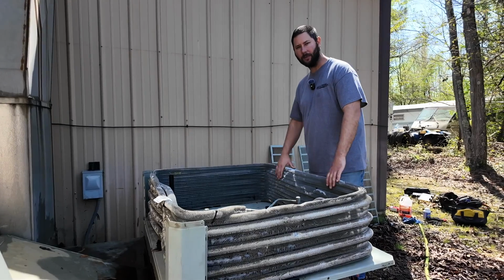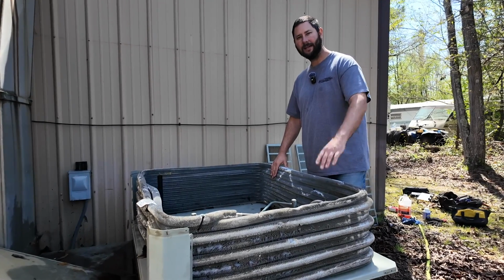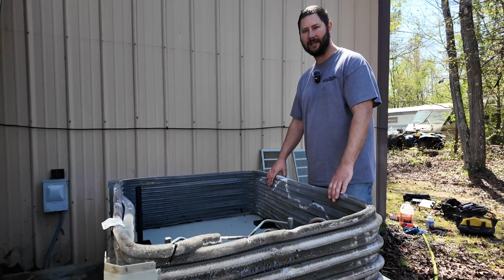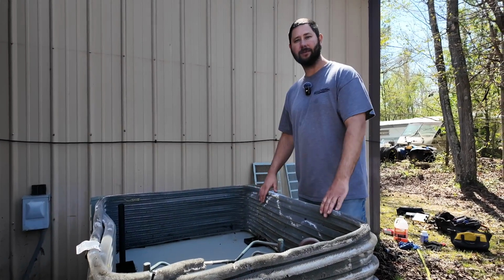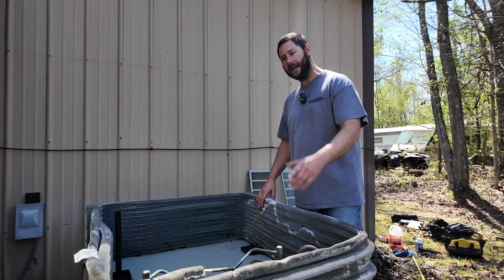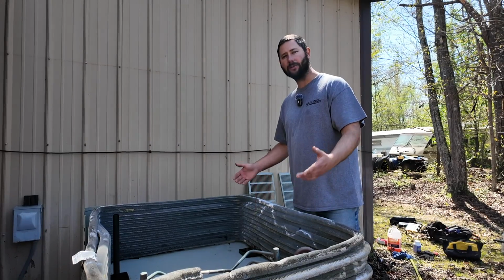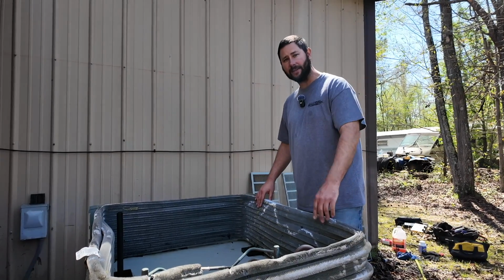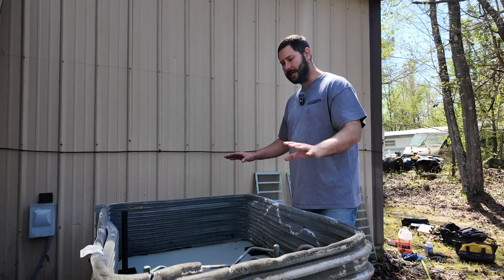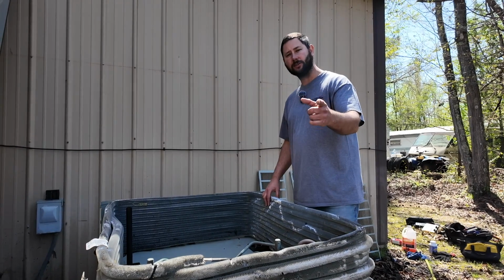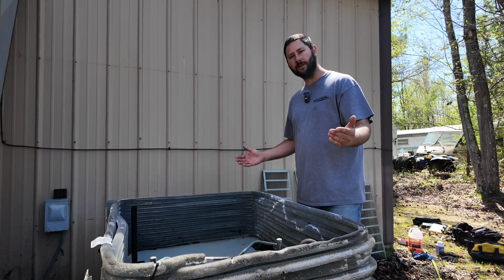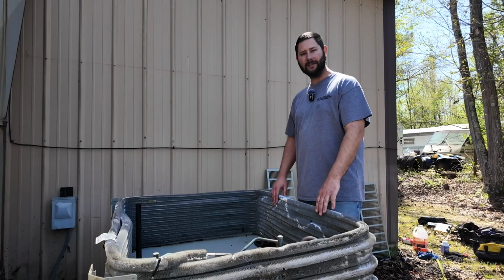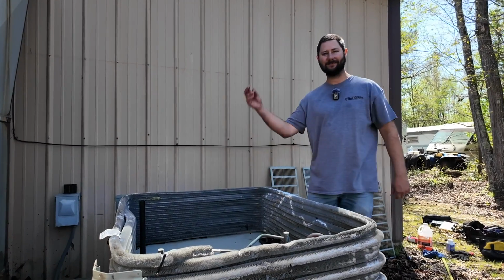The reason that it's important to keep this condenser coil clean is because this condenser coil rejects heat. And if it's dirty, it's not gonna reject heat. If it's dirty, that's gonna affect the motors. The motors are gonna pull more amps. That's gonna affect your electric bill. So if you keep this coil clean, not only will your electric bill be lower, but you will avoid costly repairs. Now, let's put this thing back together.